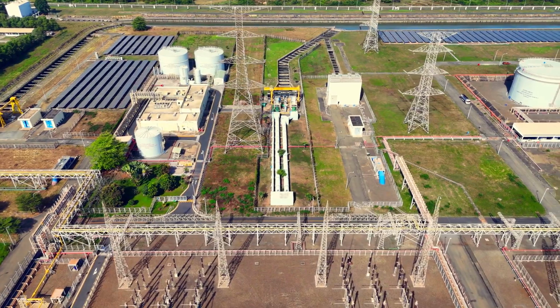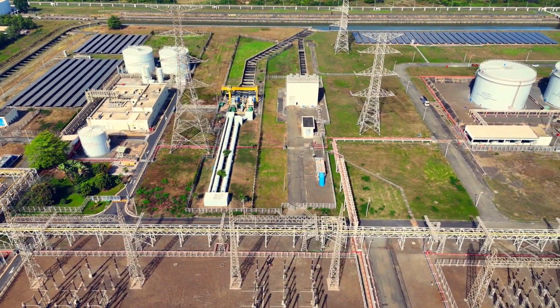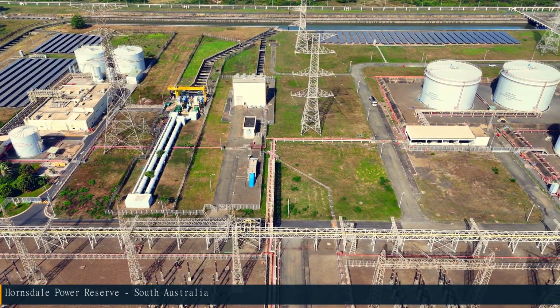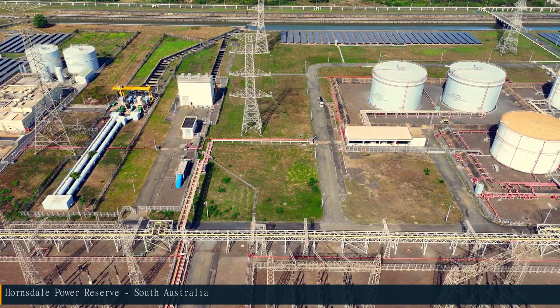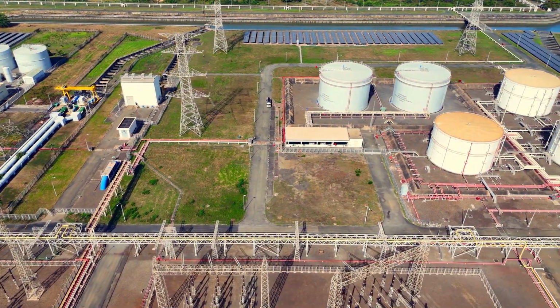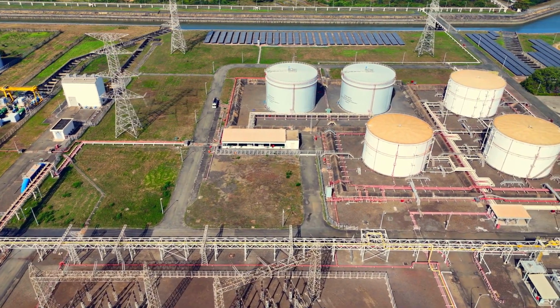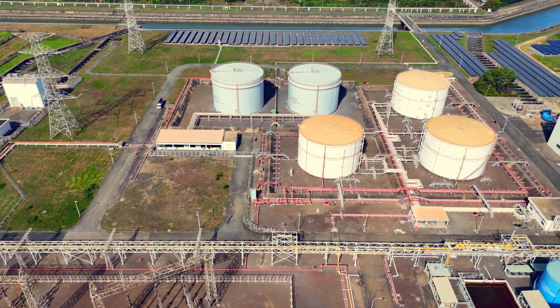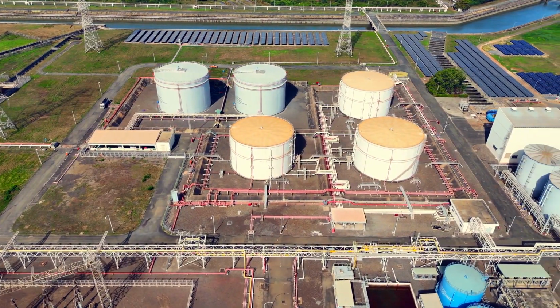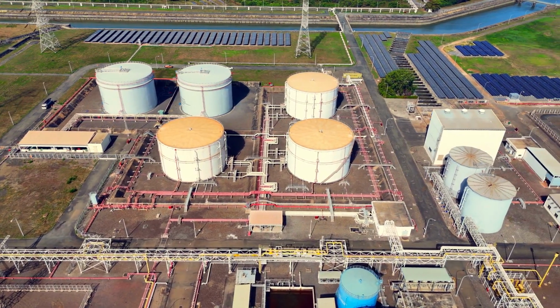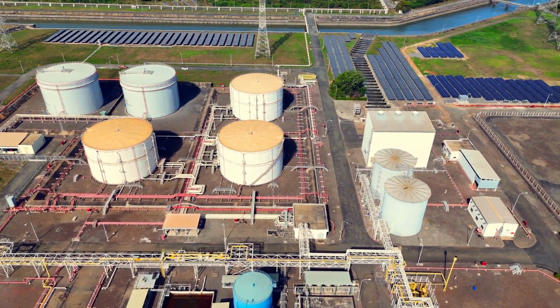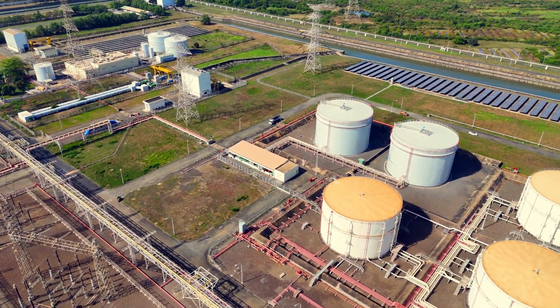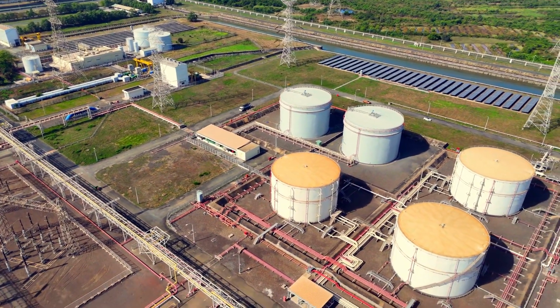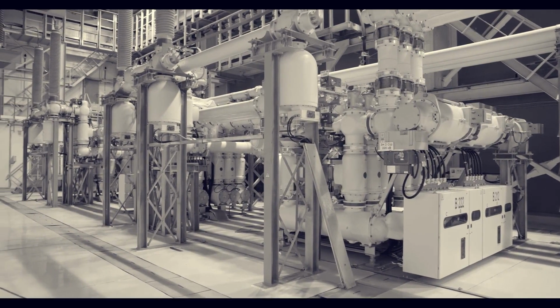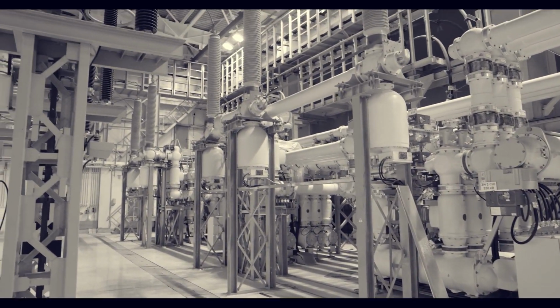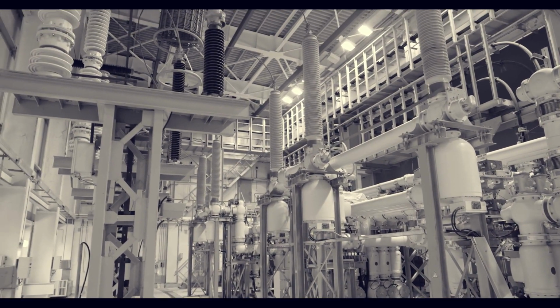Full implementation, January 2030. Separately, a technology called grid-forming inverters is being developed and slowly deployed. A conventional inverter follows the grid's voltage wave. It's a follower. A grid-forming inverter can synthesize the voltage wave itself. It can produce something that behaves like inertia. Hornsdale Power Reserve in South Australia, a large grid-scale battery, was one of the first real-world tests at scale. The results were good enough that Australia now requires grid-forming capability in new large-scale battery installations. The US does not have that requirement.